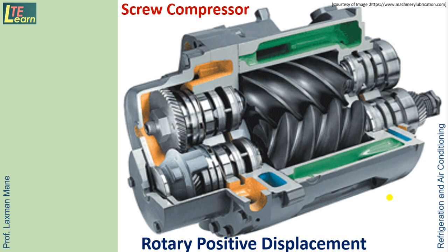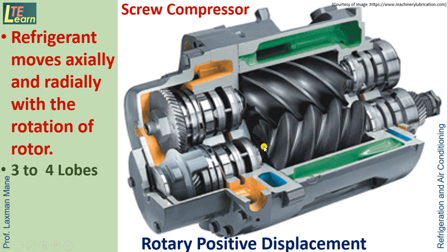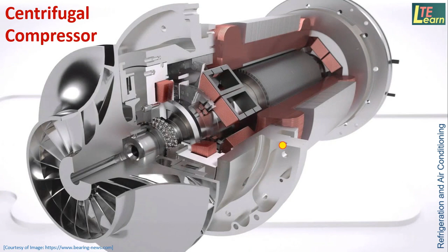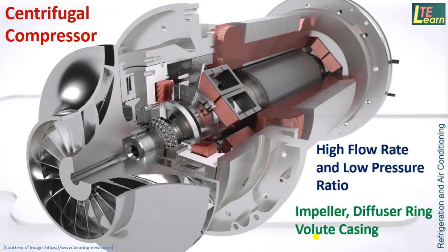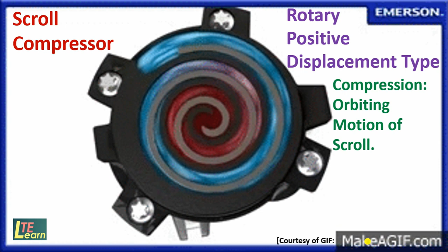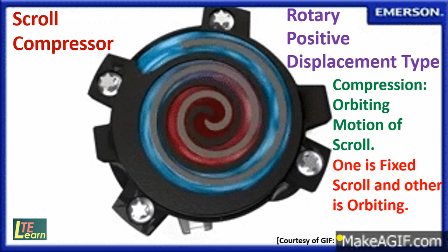Here are the different types of compressors used in central air conditioning systems. This is a screw compressor, which is a rotary positive displacement type. In this, refrigerant moves axially and radially with the rotation of the rotor. A screw compressor has 3 to 4 lobes which are rotating. The centrifugal compressor is used in case of high flow rate and low pressure ratio. A centrifugal compressor mainly consists of an impeller, diffuser ring and volute casing. The scroll compressor is a rotary positive displacement type compressor. Compression here takes place by the orbiting motion of a scroll, in which one scroll is fixed and the other is orbiting, meaning moving.